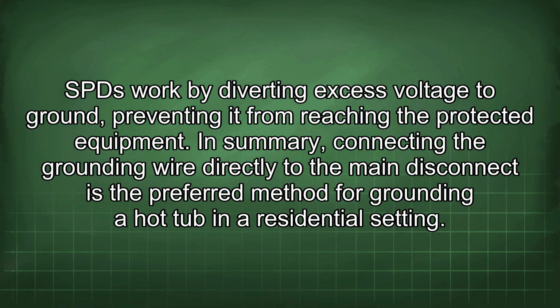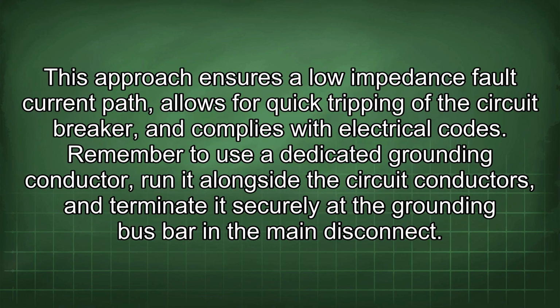In summary, connecting the grounding wire directly to the main disconnect is the preferred method for grounding a hot tub in a residential setting. This approach ensures a low impedance fault current path, allows for quick tripping of the circuit breaker, and complies with electrical codes. Remember to use a dedicated grounding conductor, run it alongside the circuit conductors, and terminate it securely at the grounding bus bar in the main disconnect.